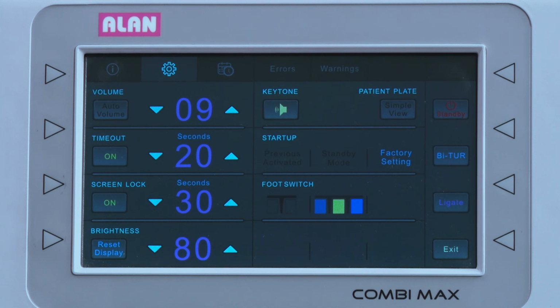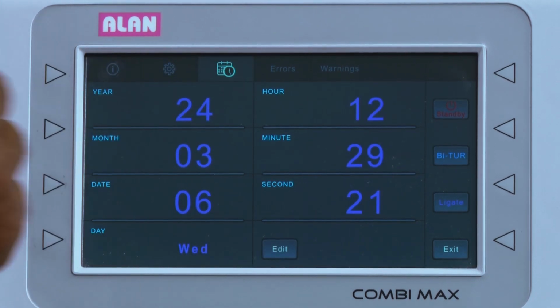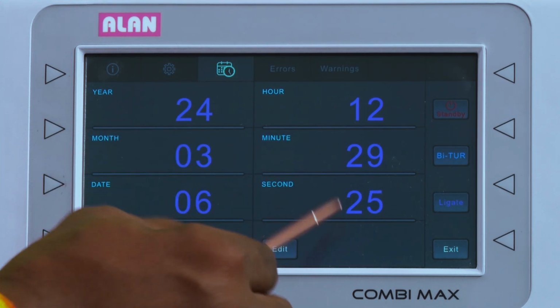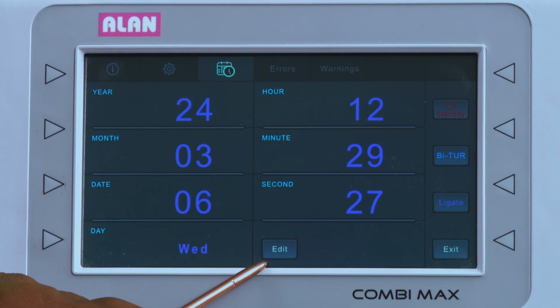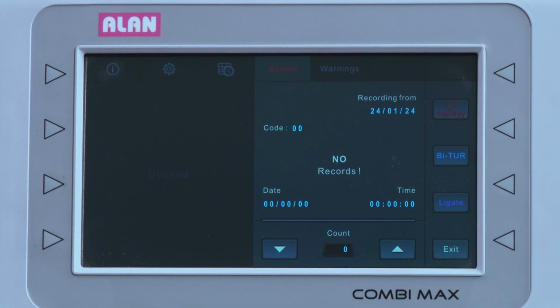To change the date and time of the unit, click on the date and time icon and change as per your requirement by clicking on edit. To see the error log, press the error icon. This error log window shows the error events that occurred in the unit with date and timestamp. Maximum 100 events are logged. To see the previous error, touch the up and down arrow key.